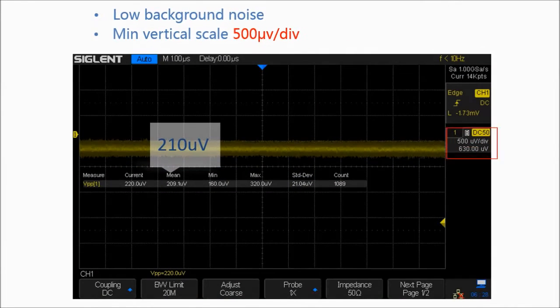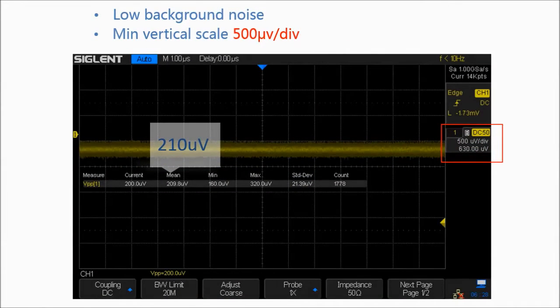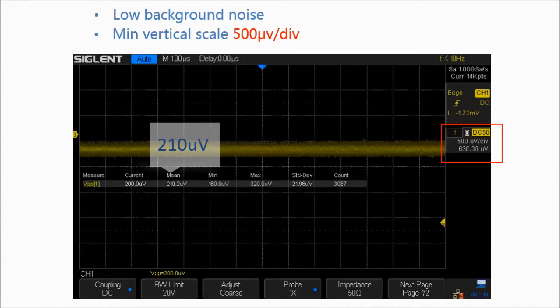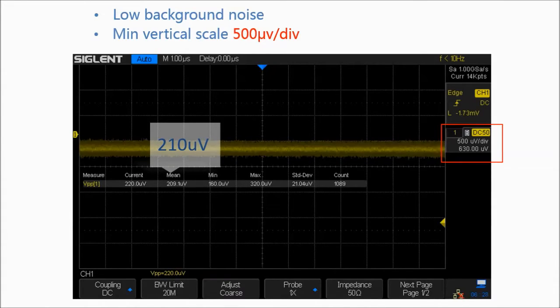The SDS1000X uses a new generation of SPO technology that has excellent signal fidelity. Its background noise is lower than similar products in the industry. The minimum vertical input range is 500 microvolt per division.